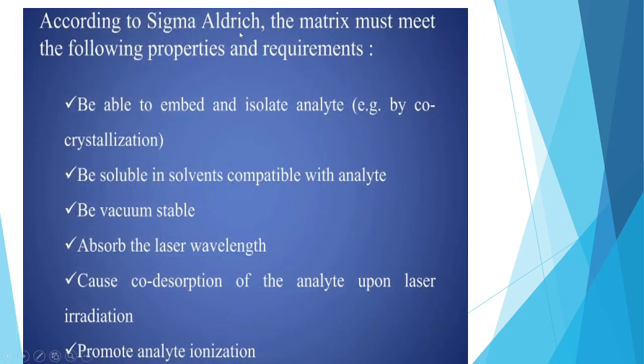According to Sigma-Aldrich, the matrix must meet the following properties and requirements: it should be able to embed and isolate the analyte by co-crystallization; be soluble in solvents compatible with the analyte (the analyte being the sample to be analyzed); be vacuum stable; absorb the laser wavelength — this is a very important property; cause co-desorption of the analyte upon laser irradiation; and promote analyte ionization.